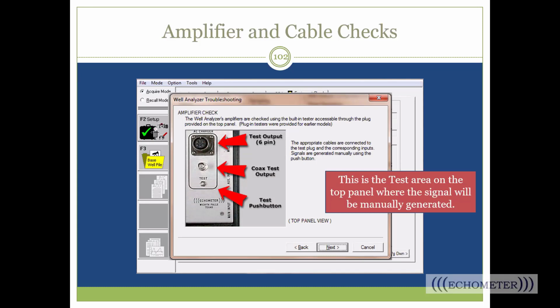Okay, so there's a test panel. If you've never really been sure what that panel is for, when you open up your well analyzer box underneath your power switch, you see this 6-pin connector, and then a little connector that looks like a microphone cable connector, and then a test button. This is a little test panel. This is where we're going to plug your cables in, one side to the top of the well analyzer and the other to the side of the well analyzer where you would normally plug in when you're acquiring data.